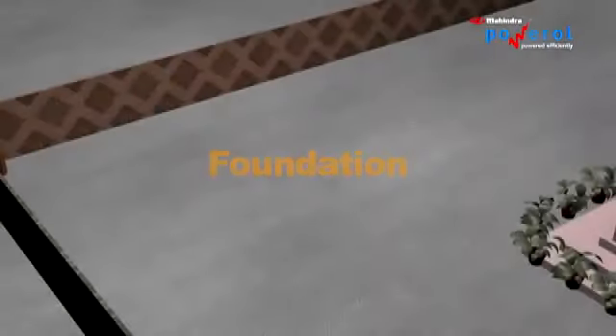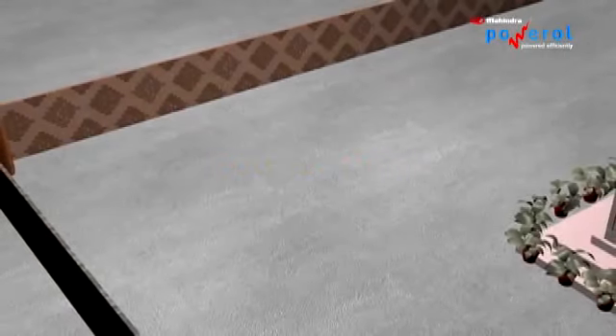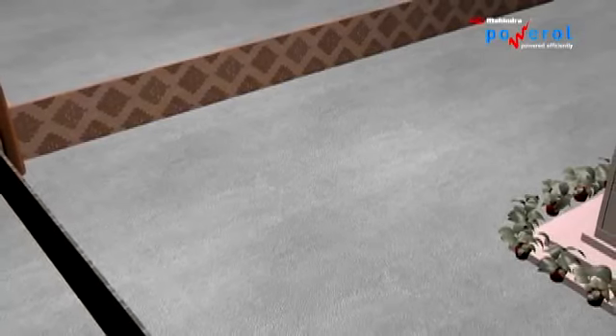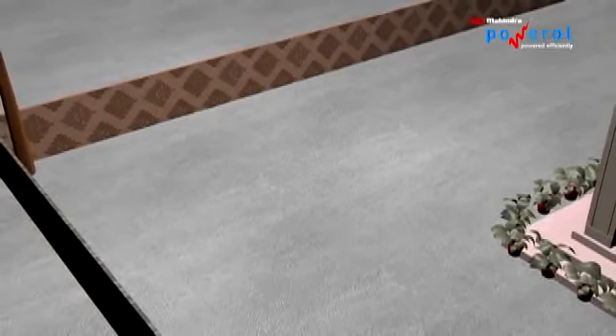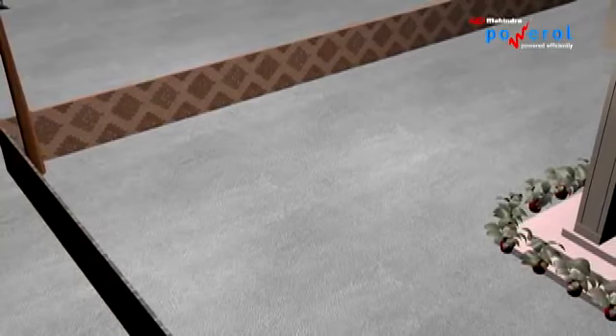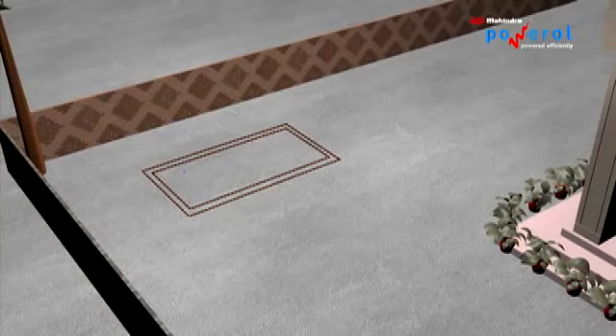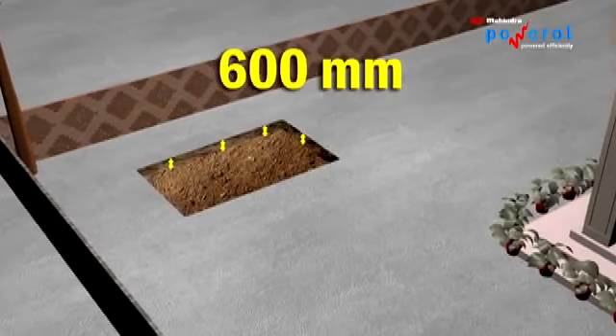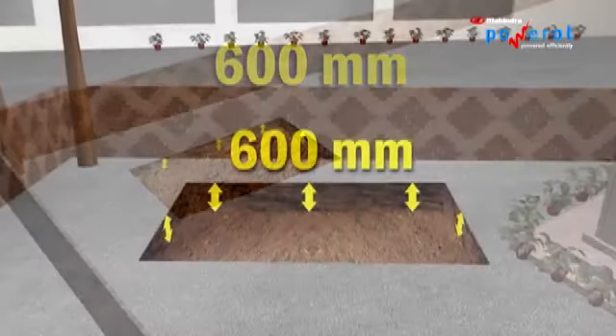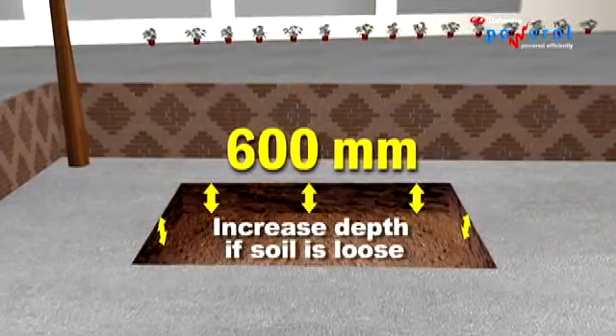Foundation. Before the arrival of the DG set, ensure a cement concrete foundation block of adequate size is made ready for placing the genset. Length and breadth minimum 12 inches more than the DG set. Depth of the concrete block should be 600 mm, and if the soil is loose, the depth may have to be increased.